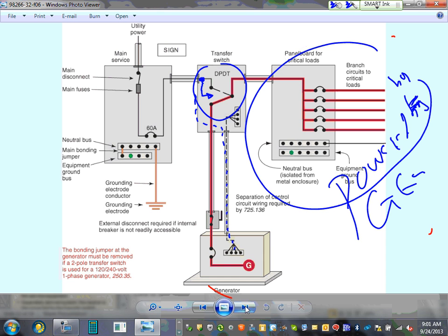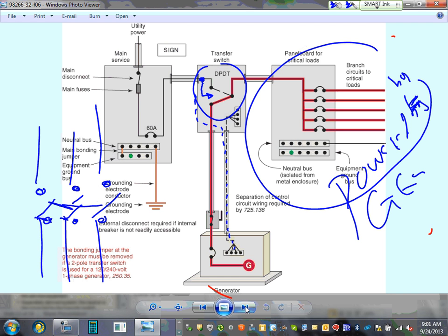So that's your generator. I want to bring to your attention, guys, you can choose to have two-pole circuit breakers or three-pole auto transfer switches. The pole really stands for this: here's one, two, three. Here's the two-pole. Two-pole is a switch. Can you guys see how my switch is coming in here? These are tied together. Here's my power. That's a two-pole circuit breaker or auto transfer switch. If you want to make it a three-pole, you put a third pole here, guys, and here's my switch, tied together, of course. And this is a three-pole circuit breaker.